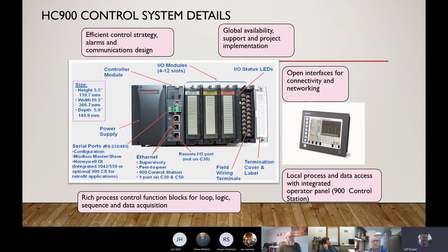Each one of the I/O cards also has an I/O status LED. Along the right-hand side, you'll have a status LED that shows if the input is good or bad, so you'll have a red or green indication. And at the very top, you also have an LED indicator that shows if the card is good or bad. So there are some very quick diagnostics you can get just by looking at the front of the HC900, without getting the software connected to it.